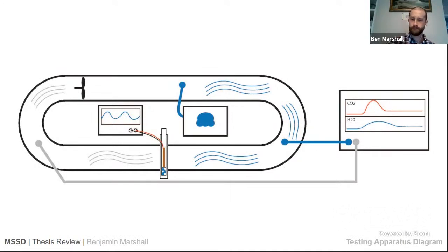I have an inlet and an outlet for the testing machine, shown here on the right. The LI-COR 7000 pulls a sample out, tests the CO2 and H2O, and puts the sample back in so that I'm not losing any air or any of the sample, so I can tell if it's soaking up water or not.